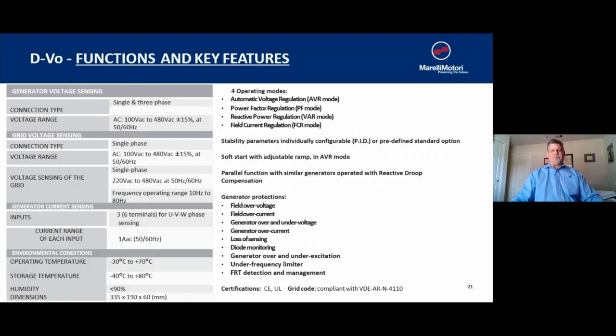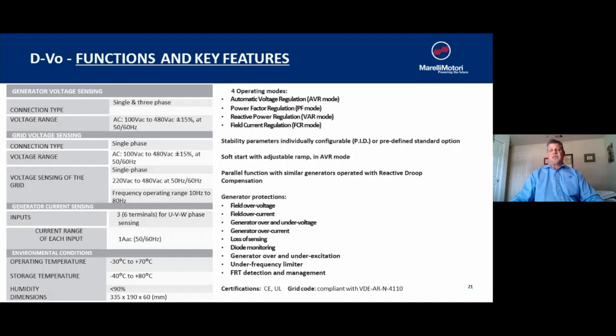The DVO is capable of either single or three-phase sensing and performs four effective operating modes: the AVR function, power factor regulation, reactive power function, and field current regulator. An additional benefit of the DVO digital voltage regulator is its built-in generator protective relay functions, including field over-voltage, field over-current, generator over-current, loss of sensing, diode monitoring, generator over/under excitation, under-frequency limiter, and FRT detection and management. In some instances, this can be utilized in lieu of protective relaying on your bus or load lines.